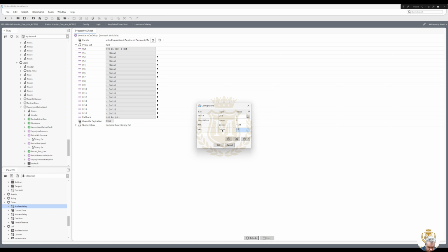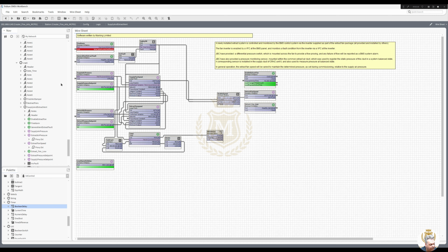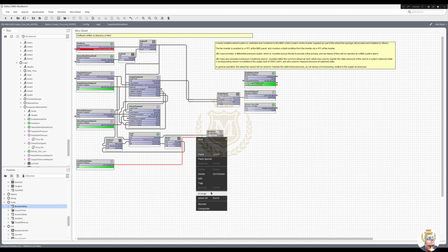We're set at no more than 120, and we still want a delay no matter what, so we'll set it no less than 30, so they can adjust it between 30 and 120. We need the numeric history in there. Actions set 30. Now I can't put that straight into there because this works in milliseconds. So if you see, if I put that straight into there, 30 milliseconds. So that's no good to me, 30 milliseconds.